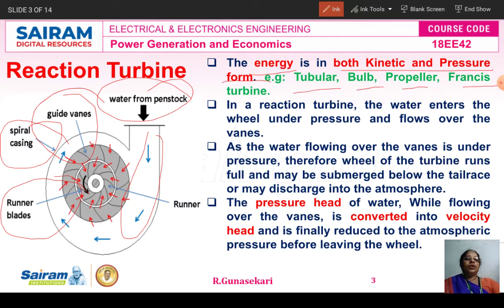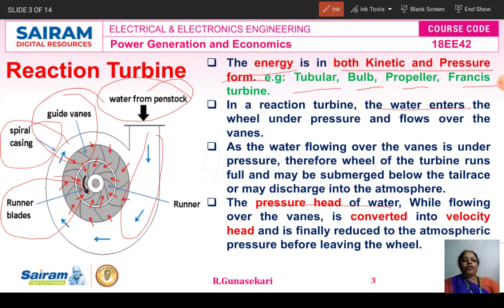In the reaction turbine, the water enters the wheel under pressure and flows over the vanes. The water flowing over the vanes is under pressure. Therefore, the wheel of the turbine runs full and may be submerged below the tail race or may discharge into the atmosphere. The pressure head of the water flowing over the guide vanes is converted into velocity head, and finally it is reduced to atmospheric pressure before leaving the wheel. This is the general concept of the reaction turbine.